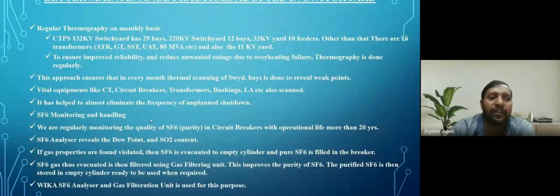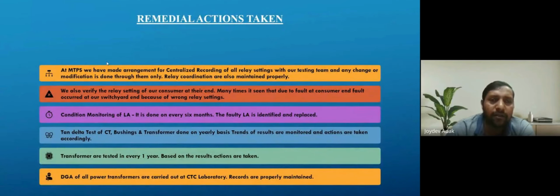So SF6 monitoring, handling, quality, thermography, and also testing of equipment on a schedule basis. Different remedial actions were taken based on the condition, LA monitoring, etc. Best practice based on the LA monitoring: for LA monitoring, we are recording the leakage current, IR value, PI value, etc. We are maintaining tan delta tests of CT, bushing, transformer on a yearly basis. Based on the trends we monitor and take action accordingly. And for transformer, DGA tests and online moisture tests are done accordingly on a schedule basis.